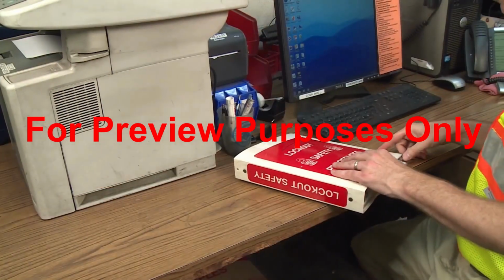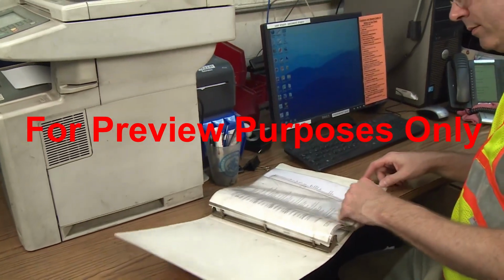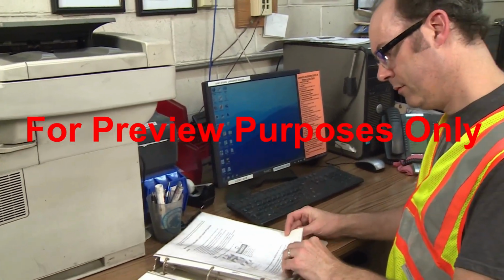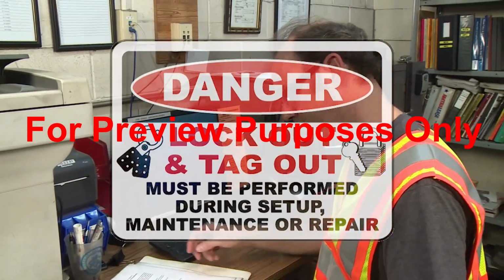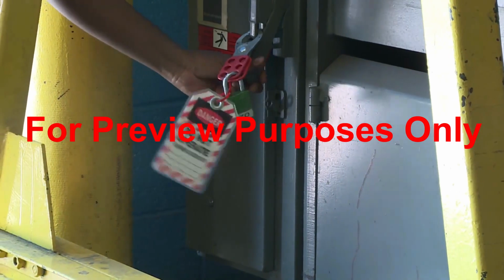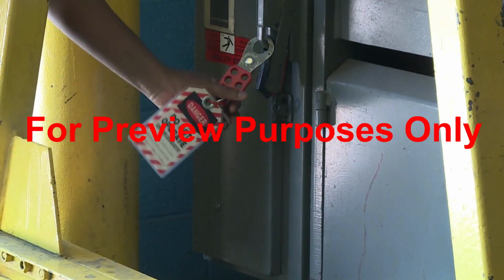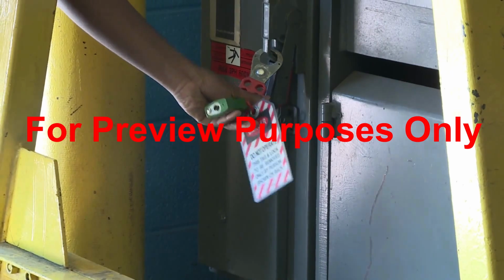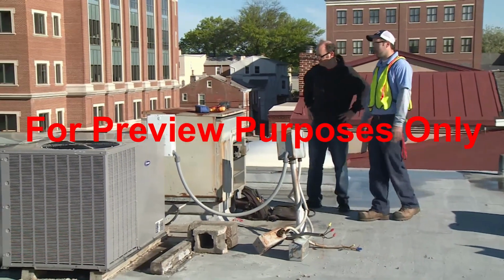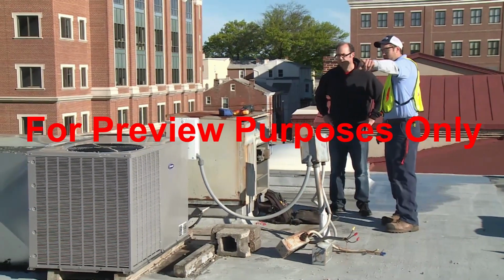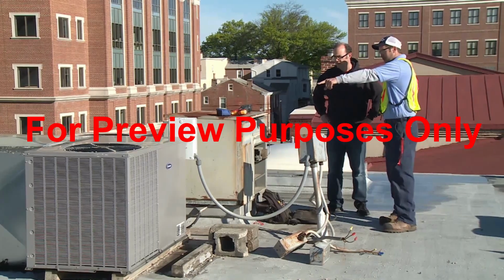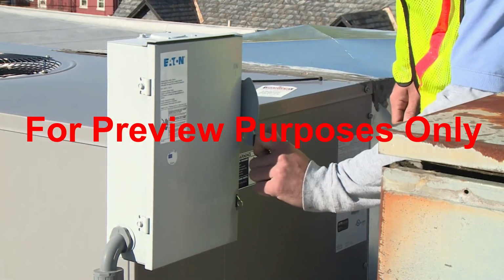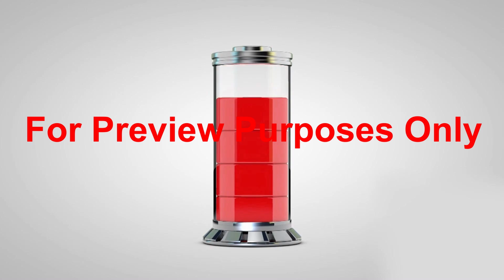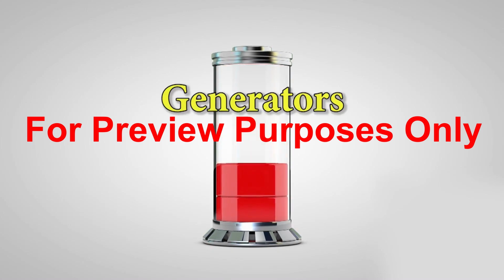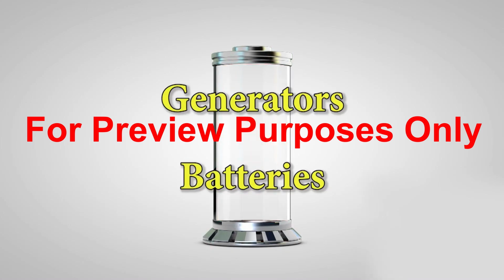To prevent this from happening, OSHA's electrical safety standards require workers to follow lockout-tagout procedures, so that when power is shut off, it can't be restored until it's safe to do so. Lockout-tagout begins with identifying all of the sources of energy to the equipment that needs to be serviced and determining how they should be shut off. This includes any backup power sources, such as generators and batteries.